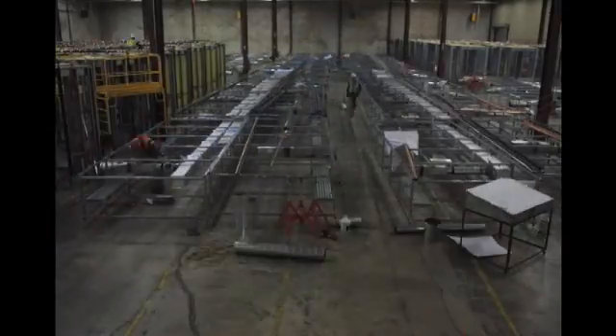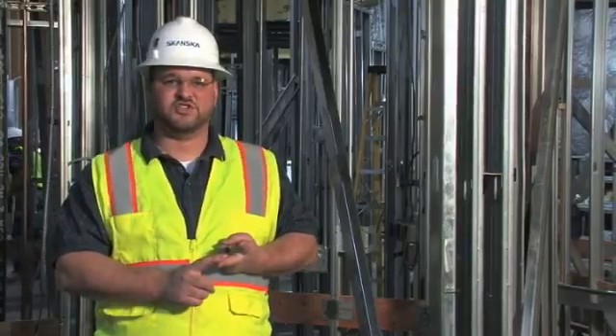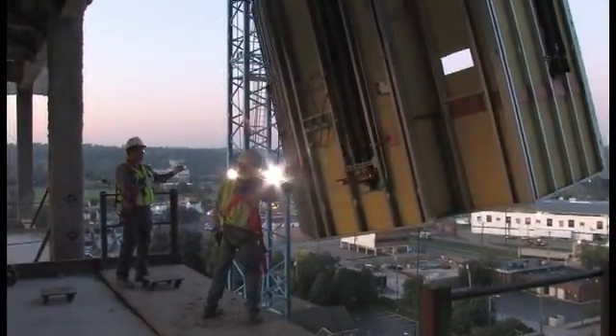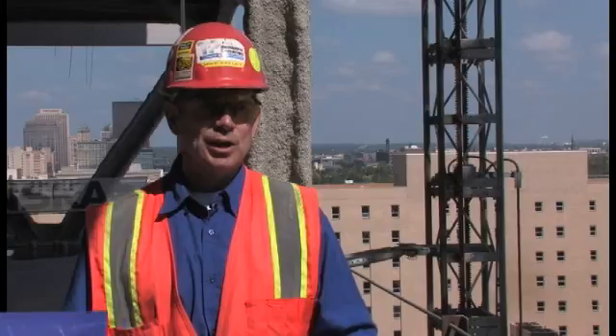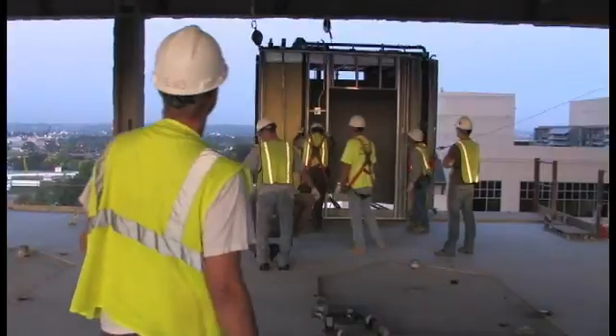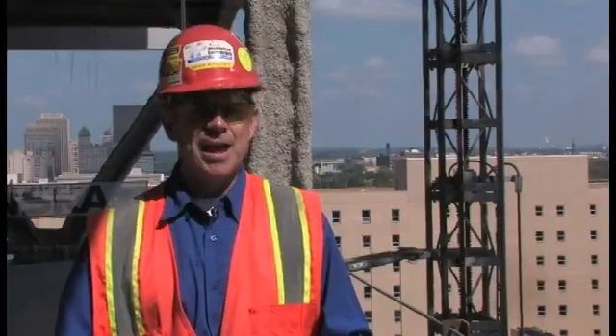In our trade, we should be able to do about 200 to 250 feet of three-quarter inch conduit a day — that's what we'd be expected to run. At the warehouse, there were some days I was getting 650 feet of pipe. Each corridor would have about 4,000 feet of pipe, which would normally take maybe two weeks for a guy to do, and it was taking me probably three days. You don't have any issues with wind, water, ice, or any of those factors. On a job this size, they'll spend an hour and a half to two hours a day of non-productive time just looking for stuff. By doing this work in the warehouse, we cut that down to 15 to 20 minutes a day.